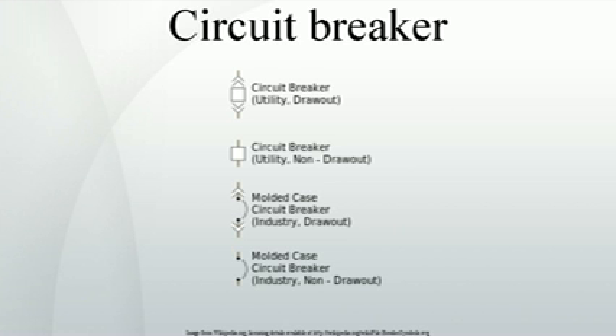International Standard IEC 60898-1 and European Standard EN 60898-1 define the rated current In of a circuit breaker for low-voltage distribution applications as the maximum current that the breaker is designed to carry continuously, at an ambient air temperature of 30 °C. The commonly available preferred values for the rated current are 6A, 10A, 13A, 16A, 20A, 25A, 32A, 40A, 50A, 63A, 80A, 100A, and 125A, Renard series, slightly modified to include current limit of British BS 1363 sockets.